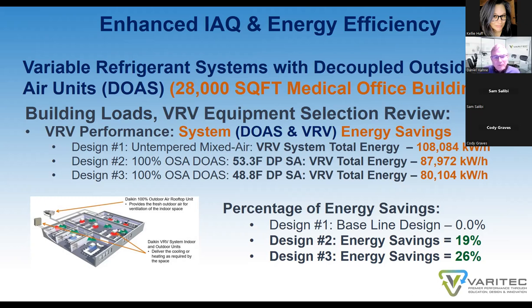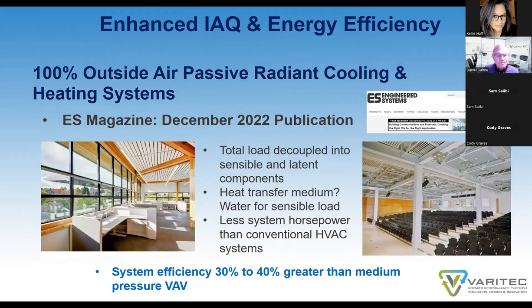And the energy efficiency became quite apparent, how low dew point, 100% outside air, variable refrigerant systems offered the greatest operational savings while providing the proper amount of outside air to each zone, or more if an owner prefers to have more outdoor air to create even healthier environments.